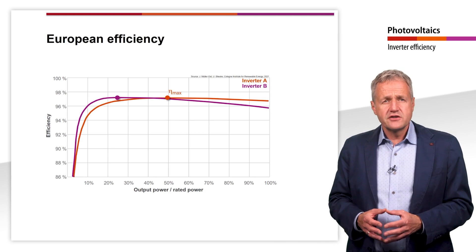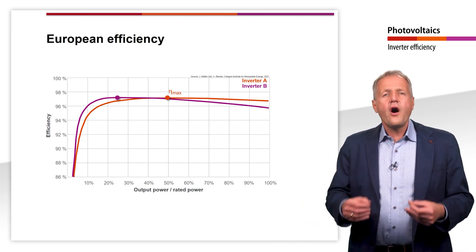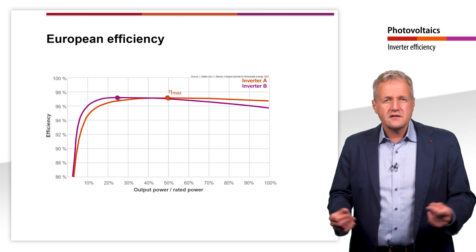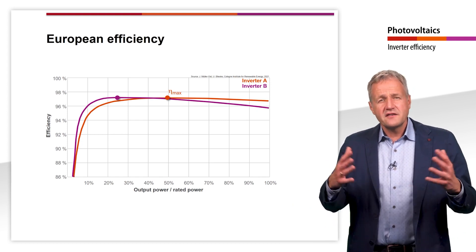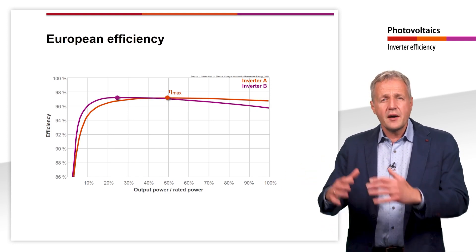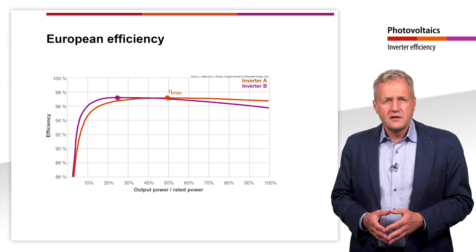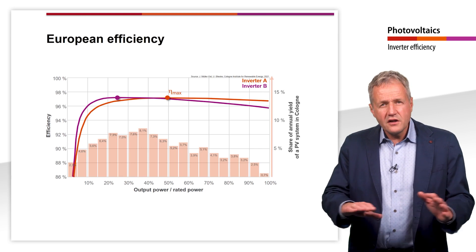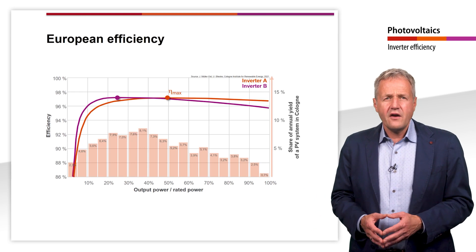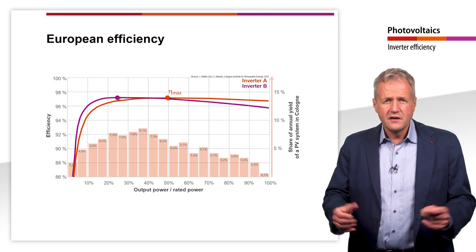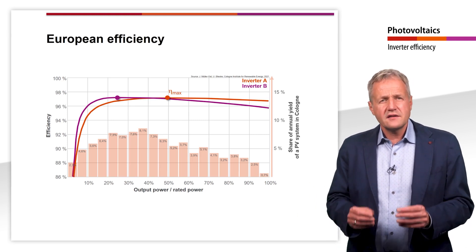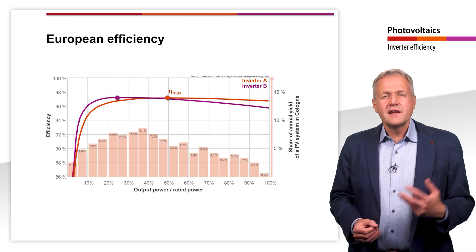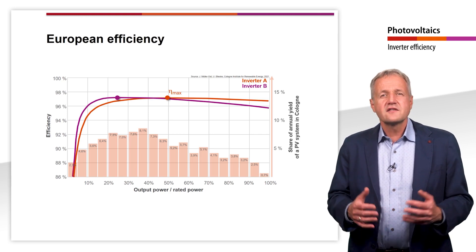Hence, we need an indication of what efficiency can be achieved with each of the two inverters over the course of a year. But how can such an average efficiency be determined? First of all, we need to know how often the different output powers are likely to occur over the course of a year. This depends very much on the irradiation and thus on the location of the PV system. A plant in the Sahara will operate much more frequently at its rated power than a plant in Germany. Looking at the example of a plant in Cologne, Germany, we see that the inverter delivers only a fraction of the annual yield at its nominal power. Most of the time, the inverter is operated in the lower partial load range. This diagram clearly shows how important a good partial load behaviour of the inverter is at this location.